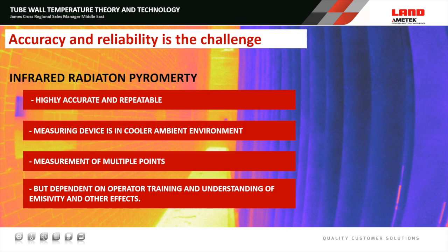Infrared radiation pyrometry is what AMETEK Land specializes in, and there are also challenges with this technology, but we have highly accurate and repeatable measurements. The measuring device itself is in the cooler ambient environment, sitting outside the reformer. We can use this technology to measure multiple points as opposed to a contact method which sits in a single location. However, the measurement is dependent on operator training and a good understanding of emissivity and other effects.